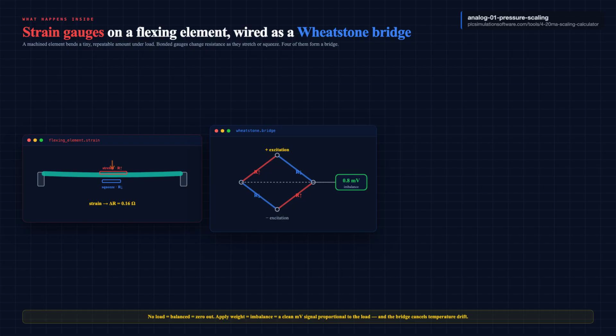4 gauges are wired into a diamond of 4 resistors. When there is no load, the bridge is balanced and the output is 0. Apply weight, and some gauges stretch while others compress. The bridge goes out of balance, and that imbalance produces a small, clean output voltage proportional to the load. The bridge also cancels out temperature drift because every gauge feels the heat together. That is the trick that makes a load cell accurate.